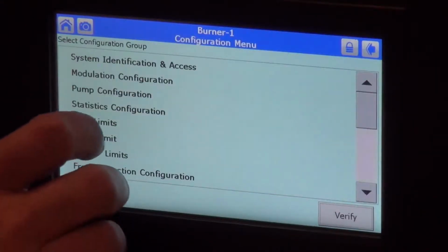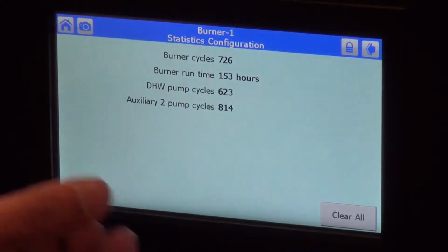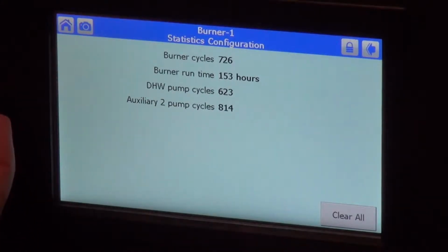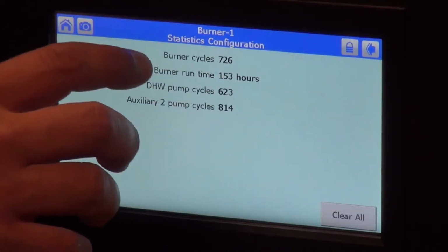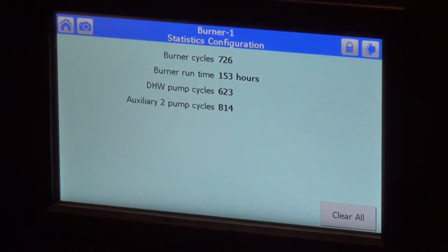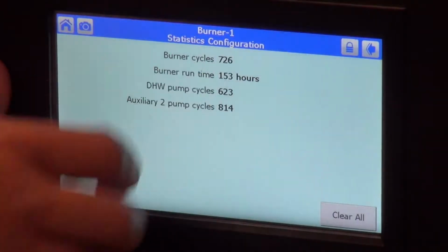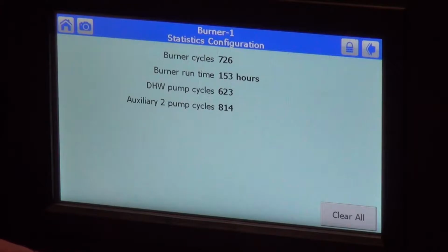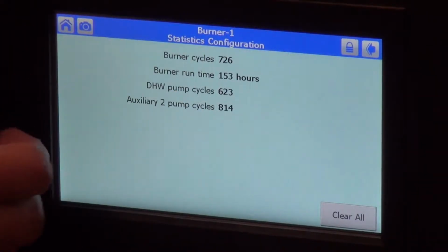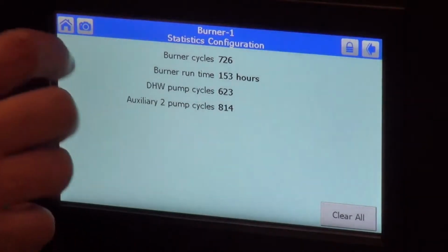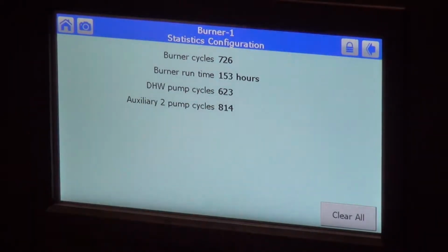We can look at statistics configurations. So the statistics configuration is actually going to give you the run cycle. So you can see this guy's ran 726 cycles. It's done a boiler run time of 153 hours. The pump cycle 623 cycles, and then auxiliary pump cycles 814 cycles on here. This is good for periodic maintenance on there. If we're going to flush that heat exchanger out, make sure we've got stainless steel heat exchangers in here. They've got a 5-year warranty to them.